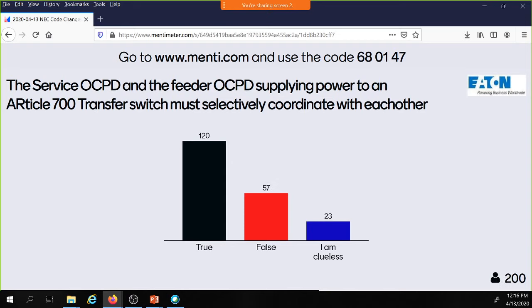I'm going to explain this, and some changes around selective coordination in the 2020 version clarified this. But the elevator speech is those two devices that are on the normal side of the transfer switch are not in the life safety Article 700 system. They're not covered by Article 700, so they do not have to selectively coordinate with each other. So that's the elevator speech per the NEC. We're going to dig into the details and the new informational note that was added to help you understand that.